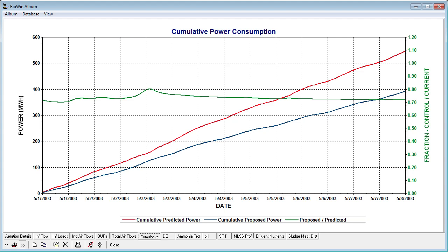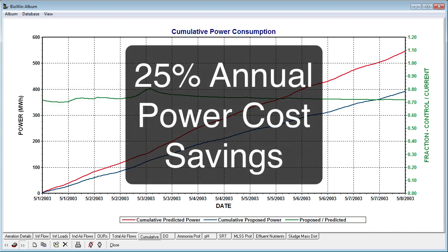It was evident that the proposed strategy's power consumption was lower than the current strategy's. A ratio of the proposed to current power consumption was plotted, and this indicated that there was a potential to save approximately 25% on power costs each year.